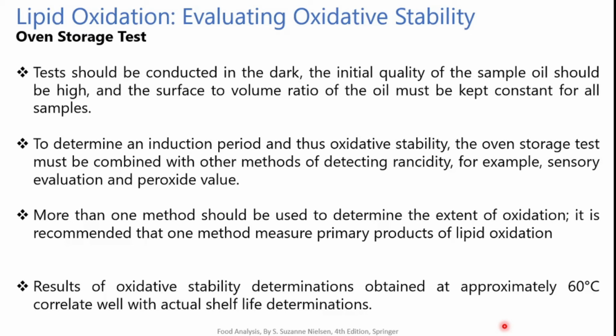The test should be conducted in the dark. The initial quality of the sample oil should be high, and the surface to volume ratio of the oil must be kept constant for all types of samples, so that we can get a proper determination.